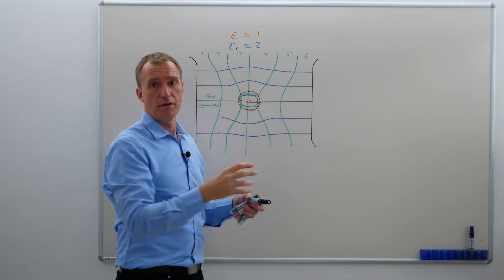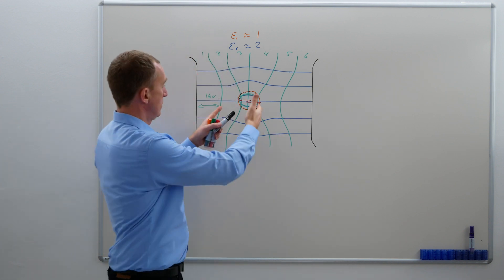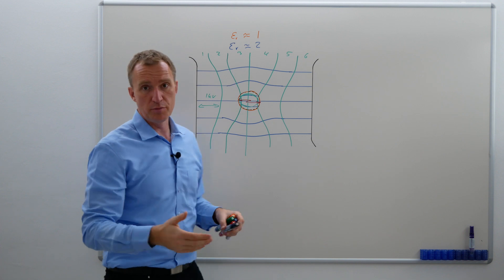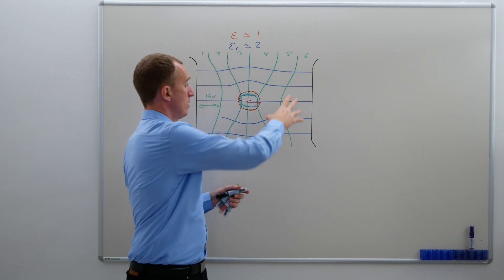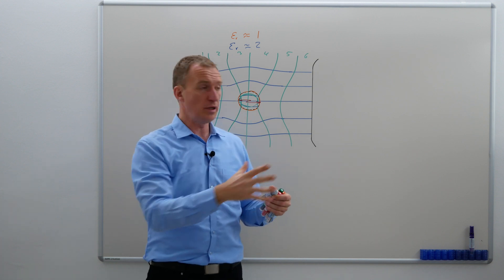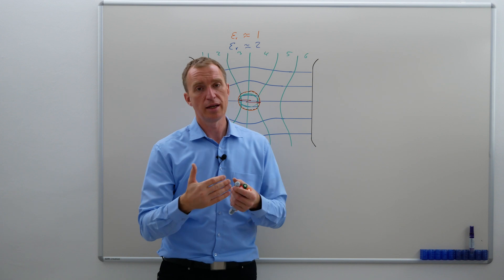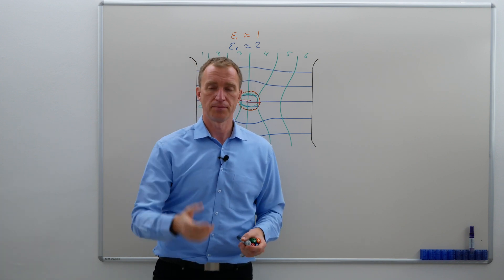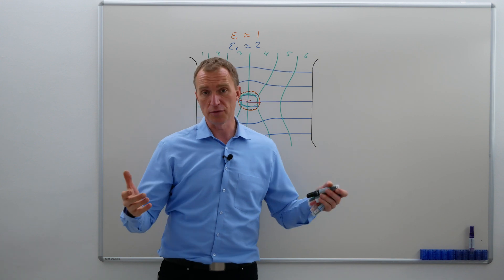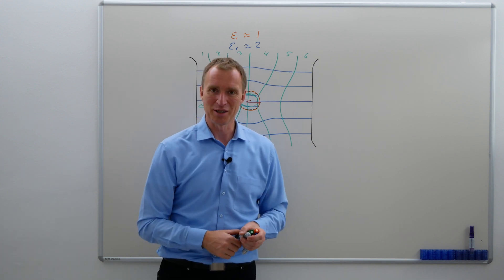we introduced a bubble of air and we just showed that this bubble of air will be exposed to an even higher electrical field than it would usually be on the solid insulation material, thus we have an elevated electric field and once again, if this is high enough, above critical, we could have partial discharges. Thank you very much for watching and if you liked that, do me a huge favor and just hit the like button. Thank you very much. Bye.